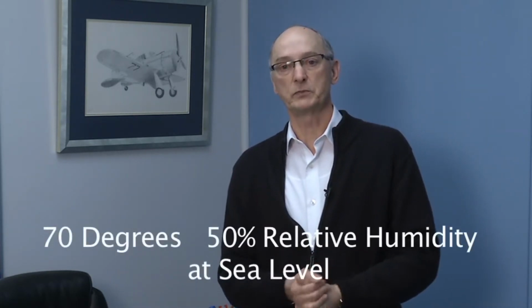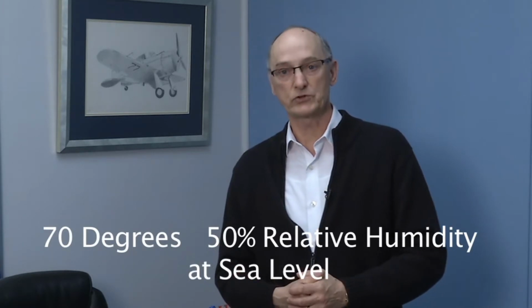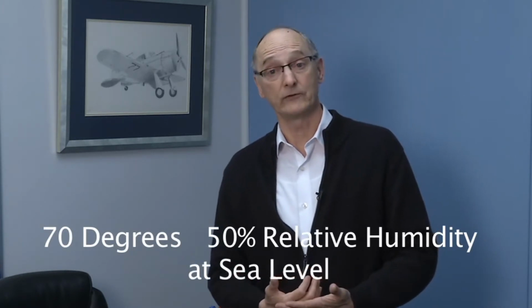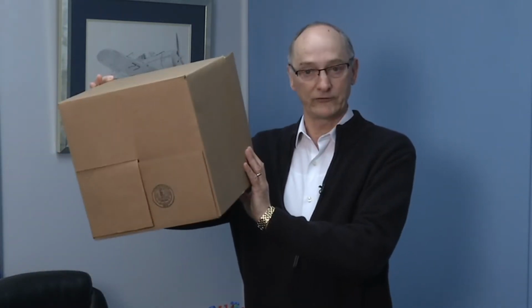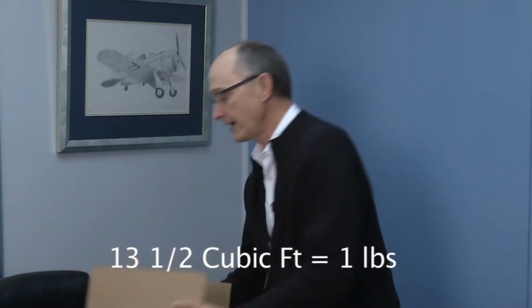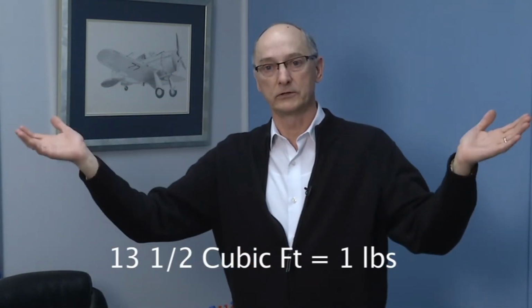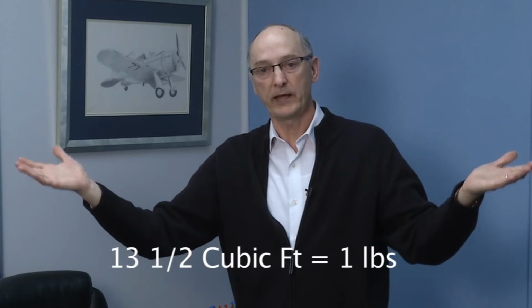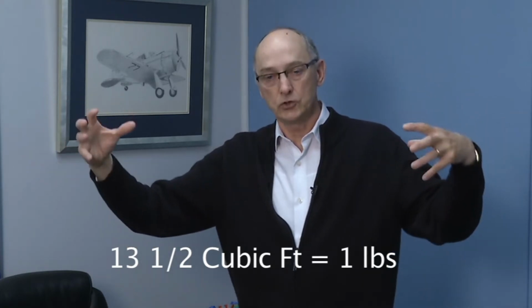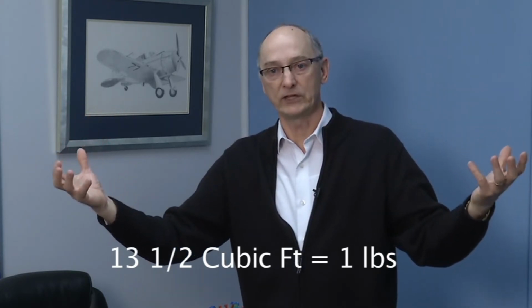Let's take an example of air, and let's start with standard conditions. Standard conditions being 70 degrees, 50% relative humidity at sea level. That air, if we had 13½ cubic feet of air, that air would weigh 1 pound. It would have 1 pound of weight to that 13½ cubic feet of air.